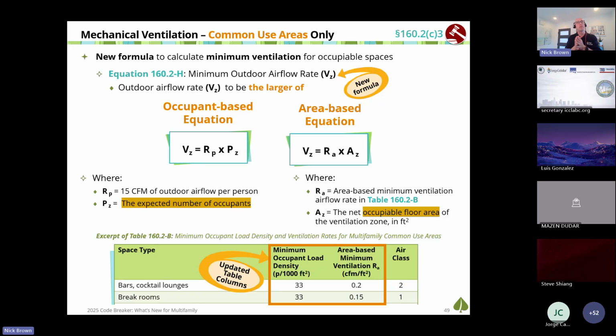Now, we just covered multifamily ventilation for dwelling units. Now let's look at code changes for common use areas. There's a new formula, and the minimum outdoor air rate is the larger of these two equations, the occupant-based equation and the area-based equation. I don't know about you, but when I've seen projects come across my desk, plan sets, I often see the engineers doing calculations on fresh air based on number of occupants that come in lower than my Title 24 derived area-based calculations. And I sometimes fight with them on that. I think this code change might help settle that, because it defines that it's to be the larger of the occupant-based equation and the area-based equation.